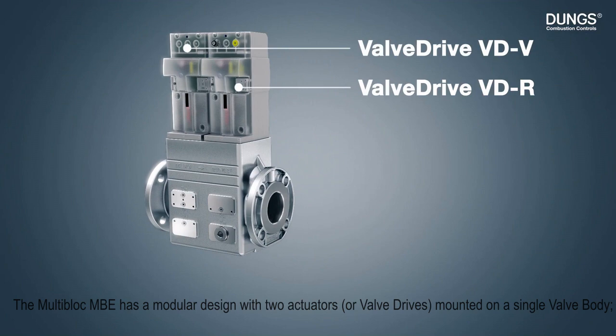The MultiBloc MBE has a modular design with two actuators or valve drives mounted on a single valve body: an on-off valve drive called VD-V, and a valve drive with an electronic regulator and downstream sensor called VD-R.